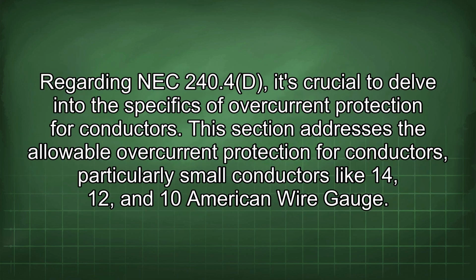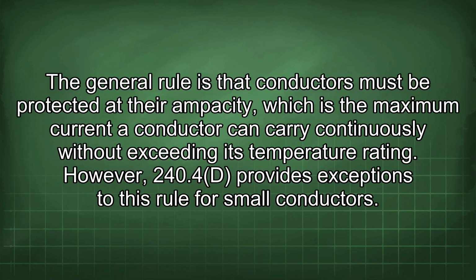Regarding NEC 240.4(D), it's crucial to delve into the specifics of overcurrent protection for conductors. This section addresses the allowable overcurrent protection for conductors, particularly small conductors like 14, 12, and 10 American wire gauge. The general rule is that conductors must be protected at their ampacity, which is the maximum current a conductor can carry continuously without exceeding its temperature rating. However, 240.4(D) provides exceptions to this rule for small conductors.